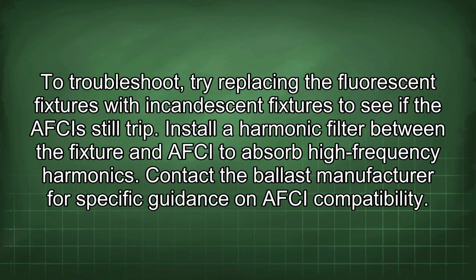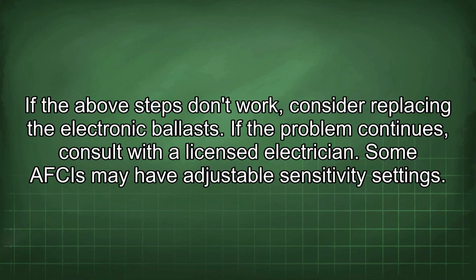Install a harmonic filter between the fixture and AFCI to absorb high-frequency harmonics. Contact the ballast manufacturer for specific guidance on AFCI compatibility. If the above steps don't work, consider replacing the electronic ballasts. If the problem continues, consult with a licensed electrician.